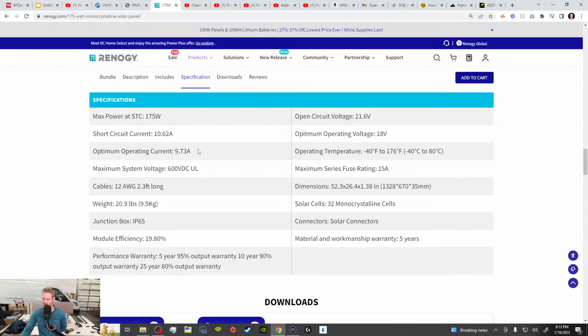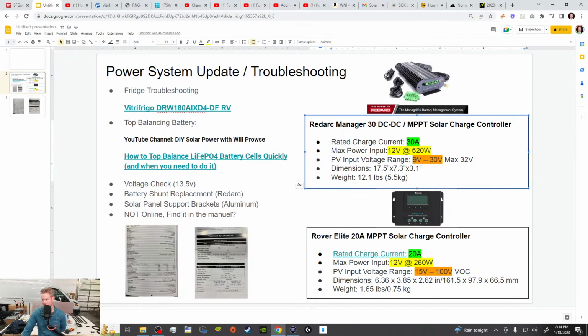We could probably sneak in a third one. So 19.46 plus 9.73 - technically for this 30 amp system, this Redarc, we could technically do 3. How do we know that's possible? Let's take 175 watts times 3, that's 525 watts. So technically by their sheet, we can't. We could do 5 100-watt panels, but if we did 3 175s, according to their specs, 525 is more than 520, and so technically we couldn't do that.